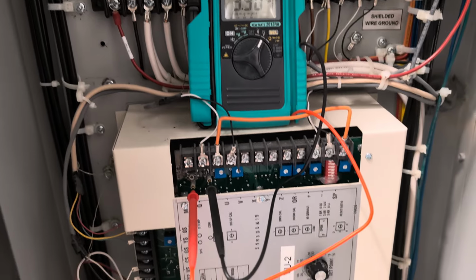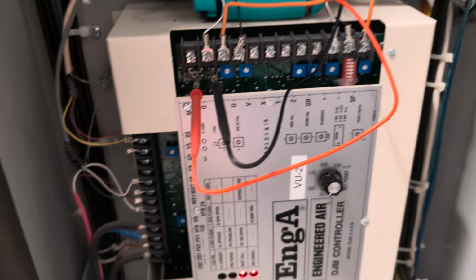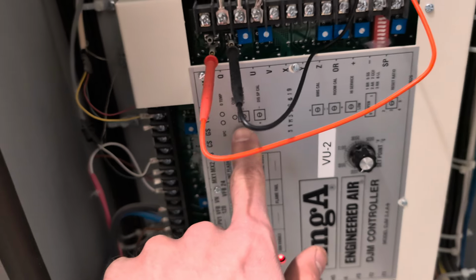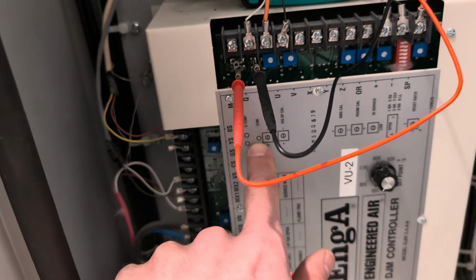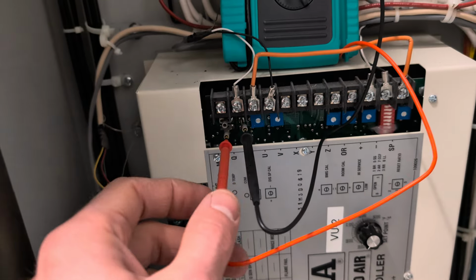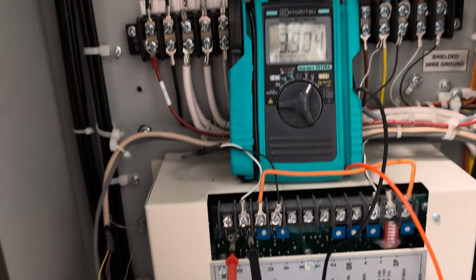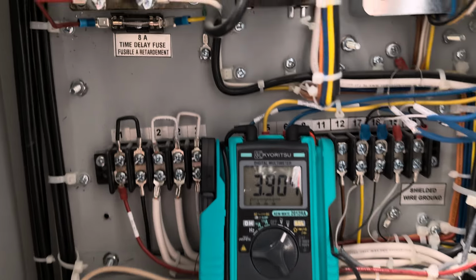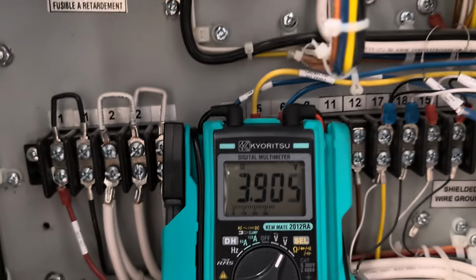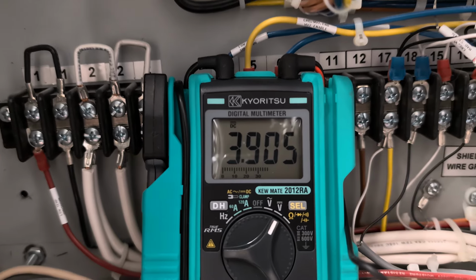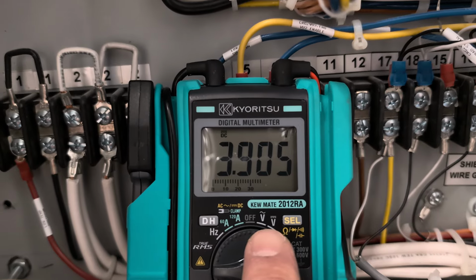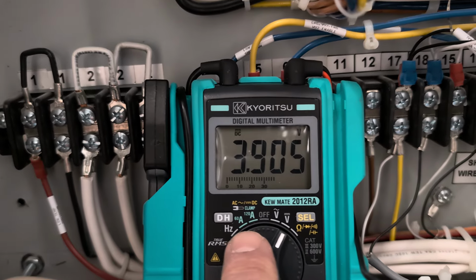But just in the short term, what you can do is this. So this is the DJM control board inside the units. You can see under here, it shows that if you put your meter into these ports, you can get a readout of the set point and the discharge air temperature. To do this, you have to set your meter to volts DC.